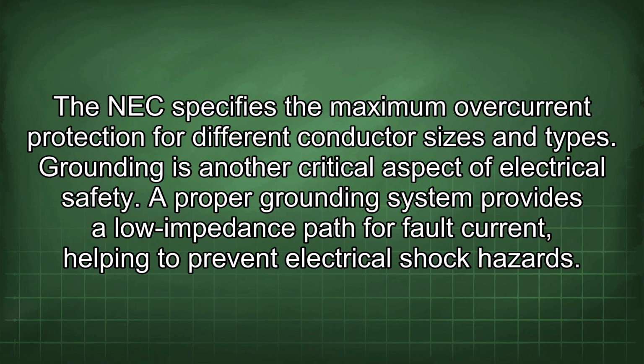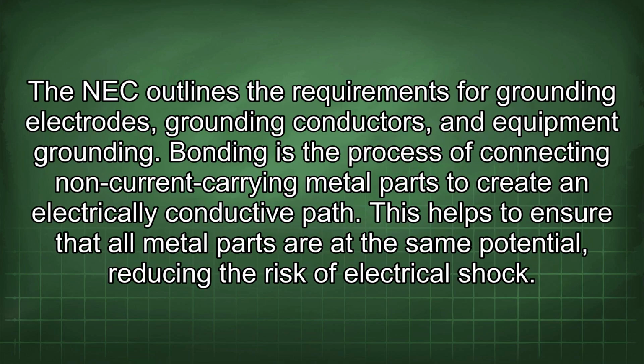Grounding is another critical aspect of electrical safety. A proper grounding system provides a low impedance path for fault current, helping to prevent electrical shock hazards. The NEC outlines the requirements for grounding electrodes, grounding conductors, and equipment grounding.